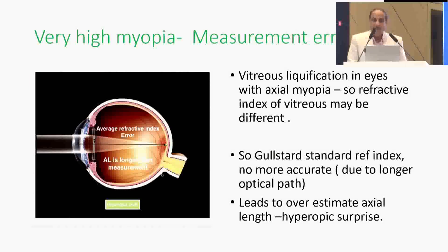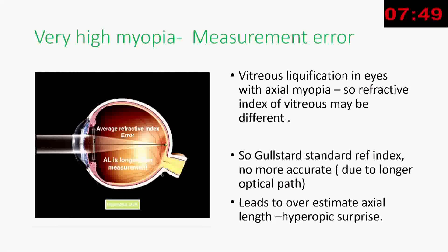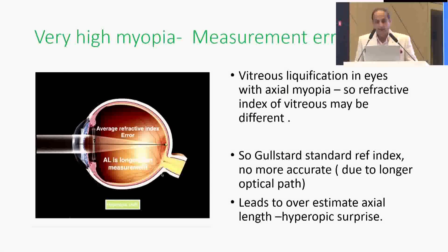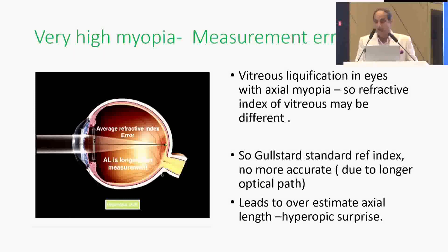Why do we have measurement errors in high myopia? There is vitreous liquefaction in eyes with axial myopia, so the refractive index of the vitreous may be different. Until now the refractive index was a one-size-fits-all, but we now understand that different parts of the eye have different refractive indices. The Gullstrand standard refractive index is no longer accurate due to the longer optical path, and it leads to an overestimate of axial length, giving a hyperopic surprise.